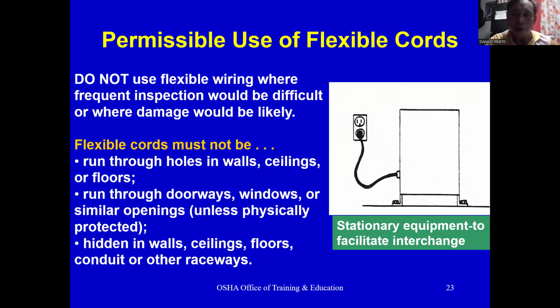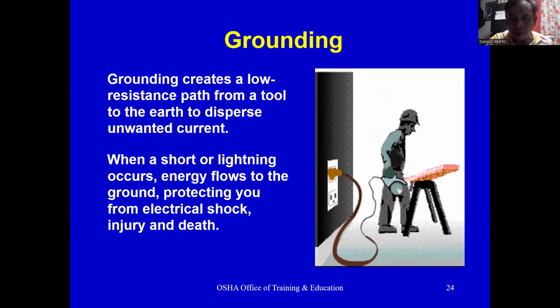Permissible use of flexible cords. Do not use flexible wiring where frequent inspection would be difficult or where damage would be likely. Flexible cords must not be run through holes in walls, ceilings, or floors, run through doorways, windows, or similar openings unless physically protected, or hidden in walls, ceilings, floors, conduit, or other raceways. Here is the example picture.